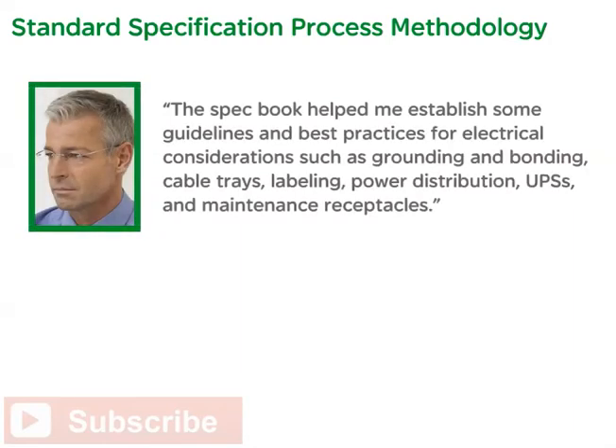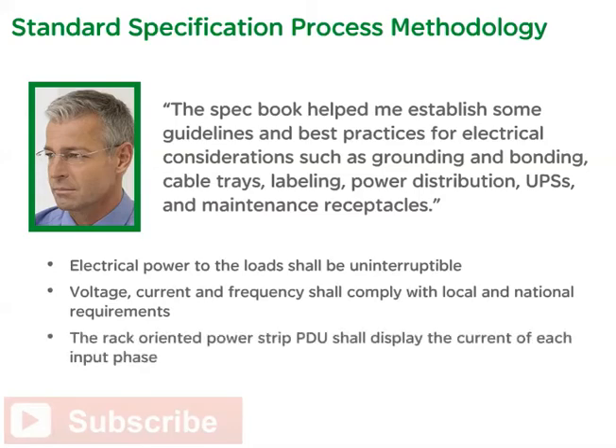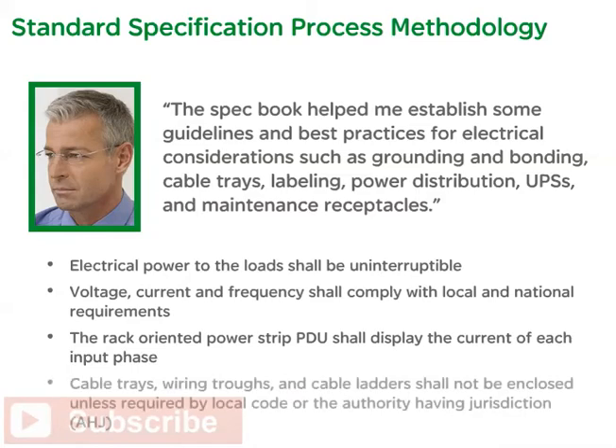The spec book helped establish guidelines and best practices for electrical considerations such as grounding and bonding, cable trays, labeling, power distribution, UPSs, and maintenance receptacles. Examples of specifications followed include: electrical power to the loads shall be uninterruptible; voltage, current, and frequency shall comply with local and national requirements; the rack-oriented power strip PDU shall display the current of each input phase; and cable trays, wiring troughs, and cable ladders shall not be enclosed unless required by local code or the authority having jurisdiction. Next, Kelly and Crawford needed to address the cooling needs in their wiring closets.